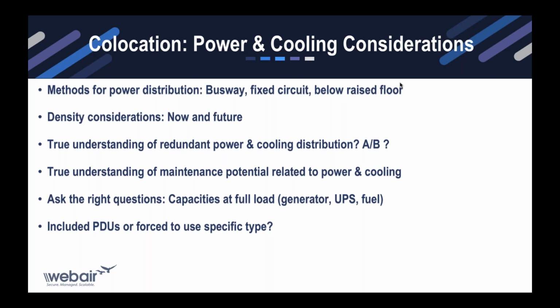The better way is over-the-rack busway distribution—long power buses where power modules or circuits can be snapped in wherever needed. The great thing is it doesn't affect the floor, and the vendor can deploy power circuits of any configuration—like 20 amp 120 volt, or 30 amp 208 three-phase—just by snapping in a box, never having to call an electrician or disrupt your existing ecosystem. It's very modular, so I'd definitely be looking for that.